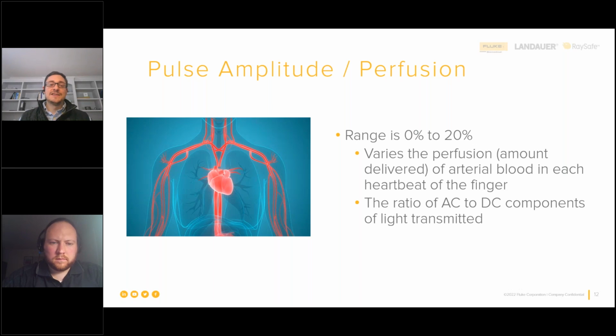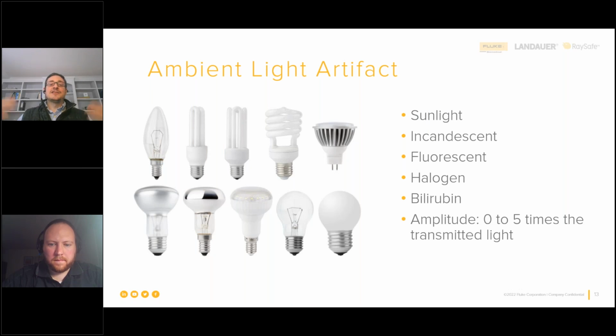Ambient light artifact is the next one. And it's extra light that could be in the patient's environment that could interfere with the SpO2 monitoring. Settings are outdoor sunlight and indoor light of various frequencies that you might encounter. But fluorescent lighting is the closest in wavelength to the red and infrared light that we talked about in that first slide. The amplitude of the extra light can be set to up to 5 times the amount of that transmitted light. And again, this monitor, the SpO2 monitor, should be able to work even with the extra light in the area.